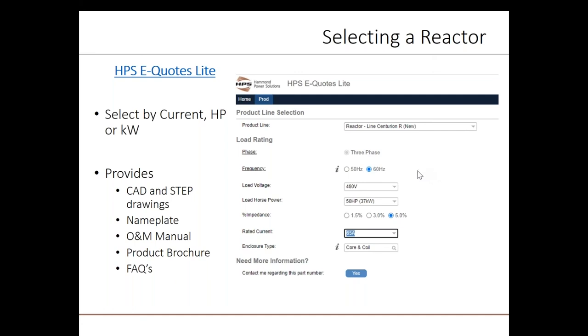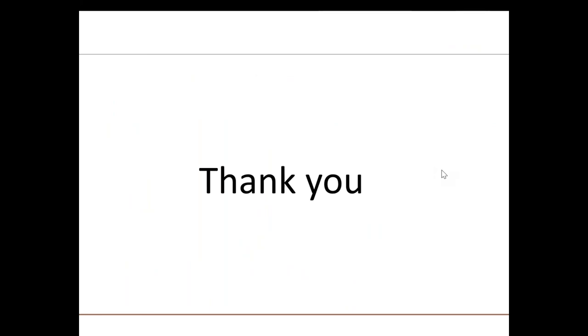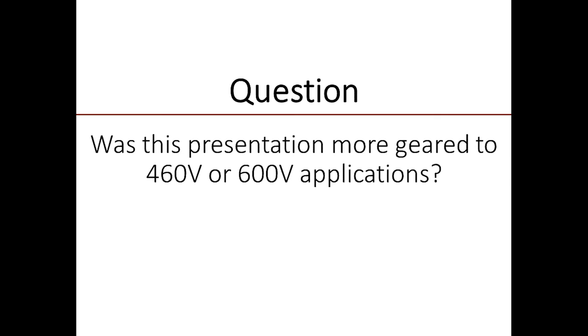Thank you for attending HPS's reactor selection presentation. I would now like to pass it back to Mike and open things up for questions. We do have one question: was this presentation more geared to 460 or 600 volt applications? The answer is it doesn't matter. Everything that we talked about today would be applied whether the system is 600 volts, 480 volts, 460, 240, or 208. All the questions, benefits, and solutions would be applicable regardless of the voltage. The only thing the voltage will change is the selection of which particular line reactor would be best suited for the application to give the correct amperage and provide the correct impedance.